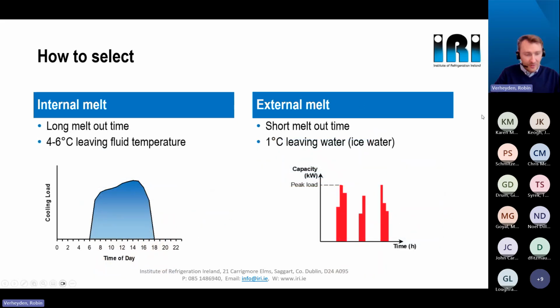So that means internal melt will deliver higher fluid outlet temperatures because of the barrier of the coil between a layer of water and the ice. It is more useful in processes with a long meltout time, for example, a typical HVAC profile, as you can see below.